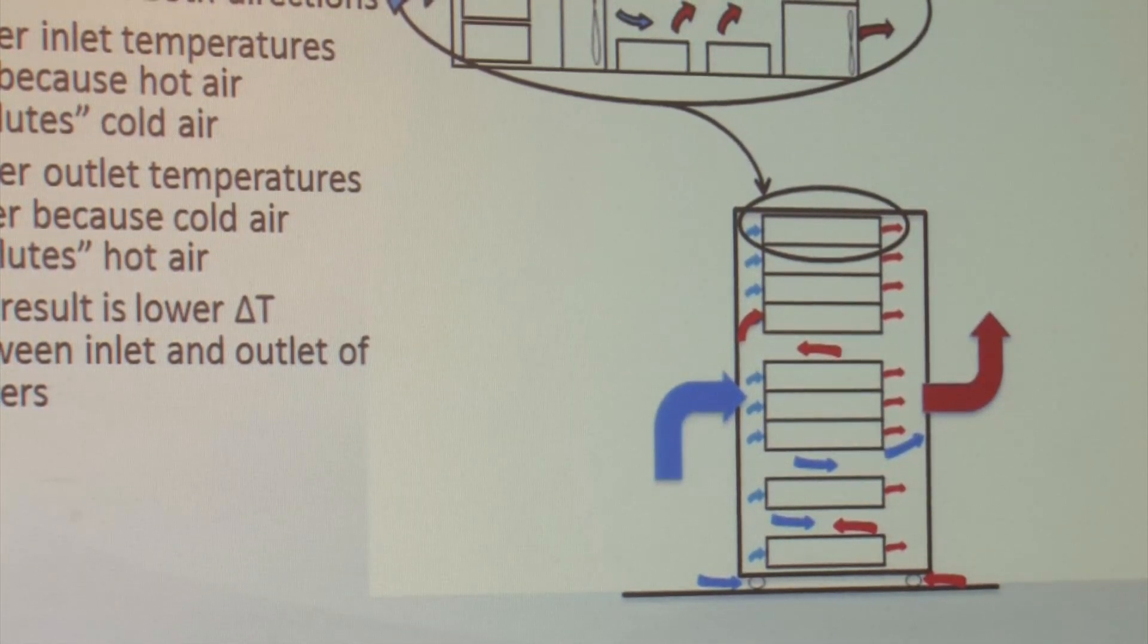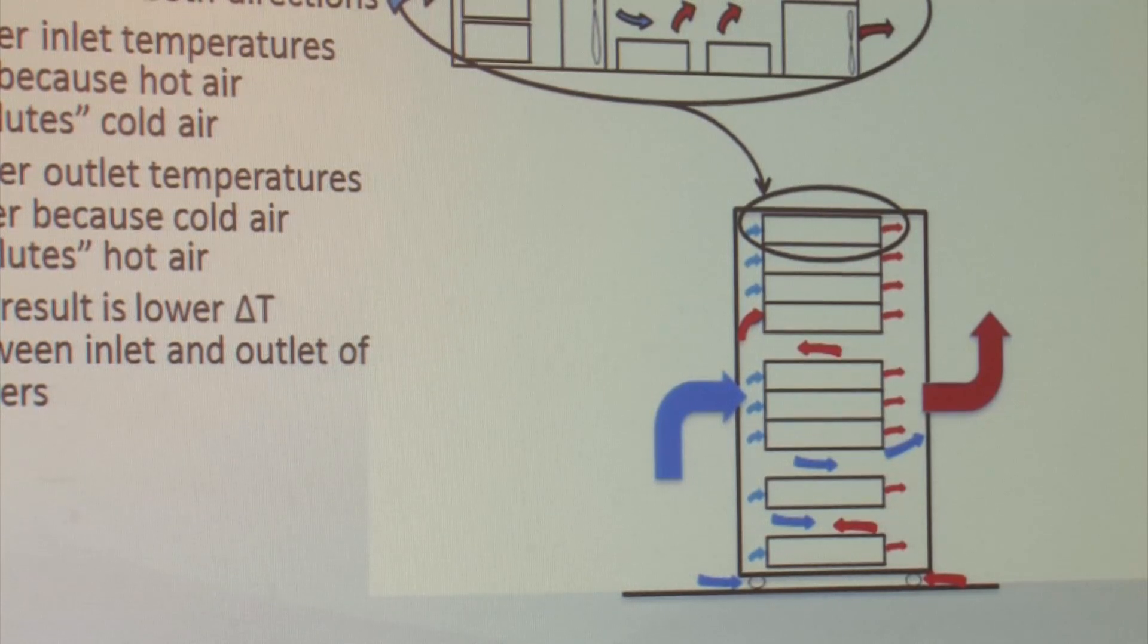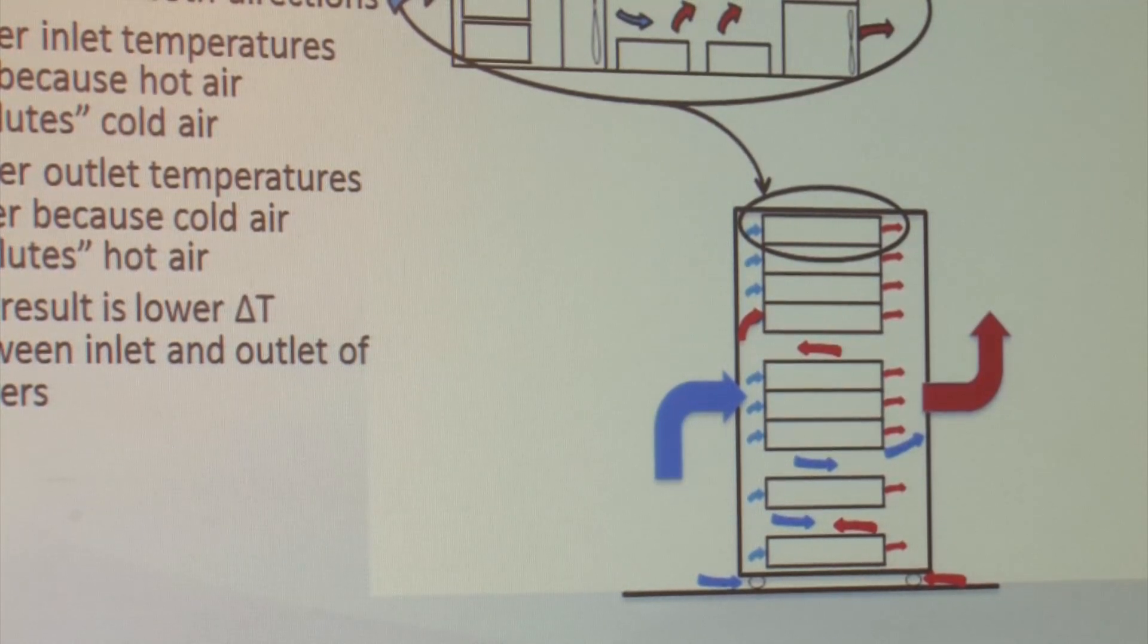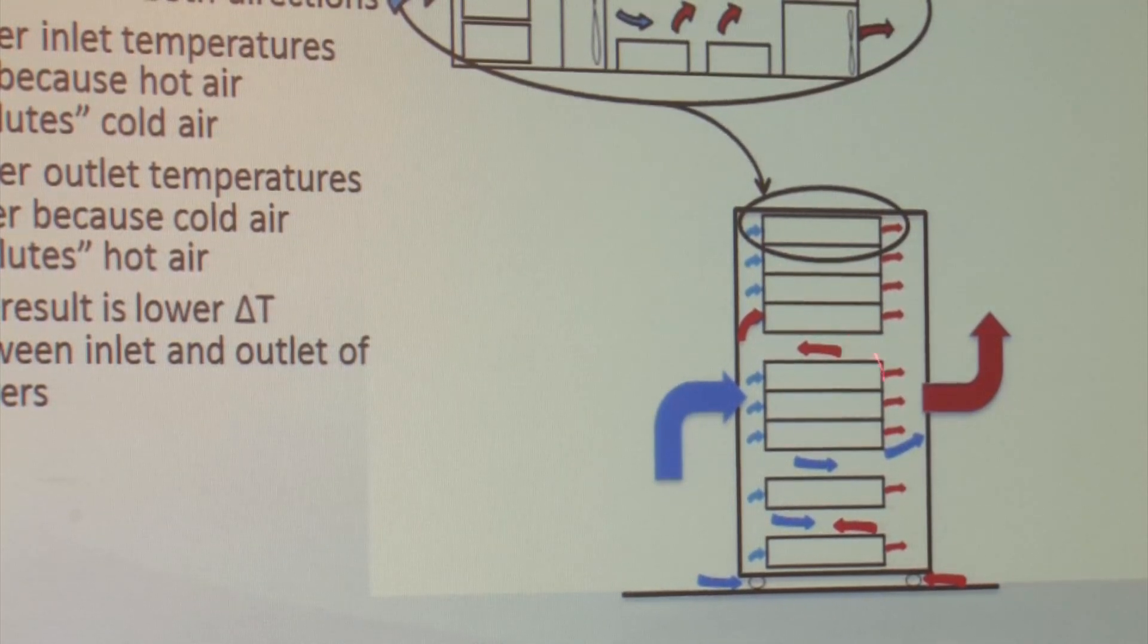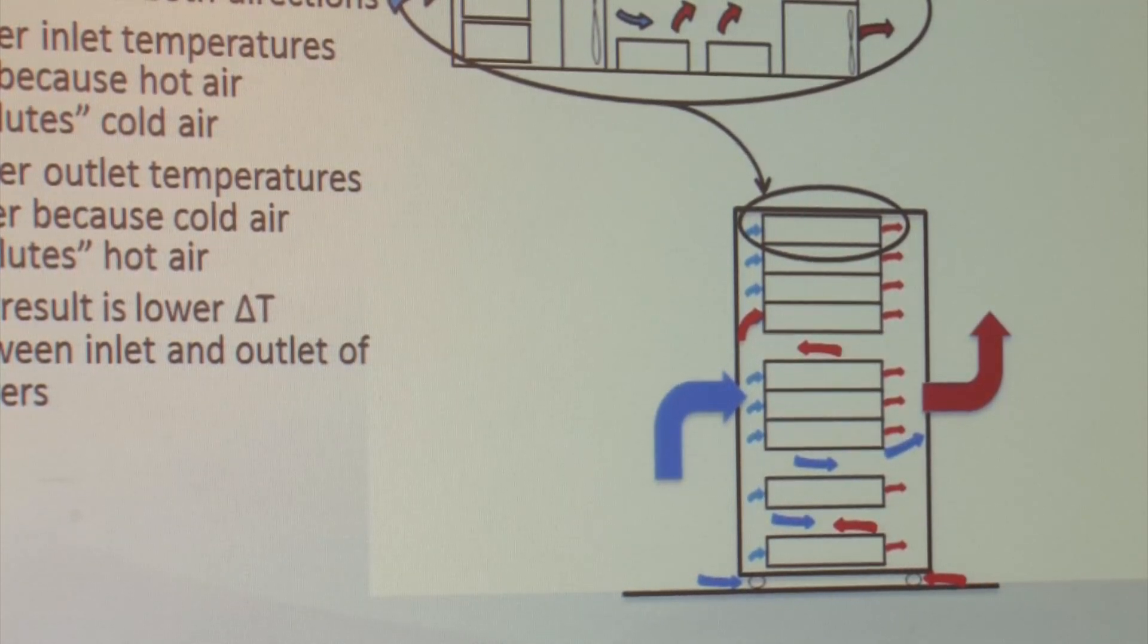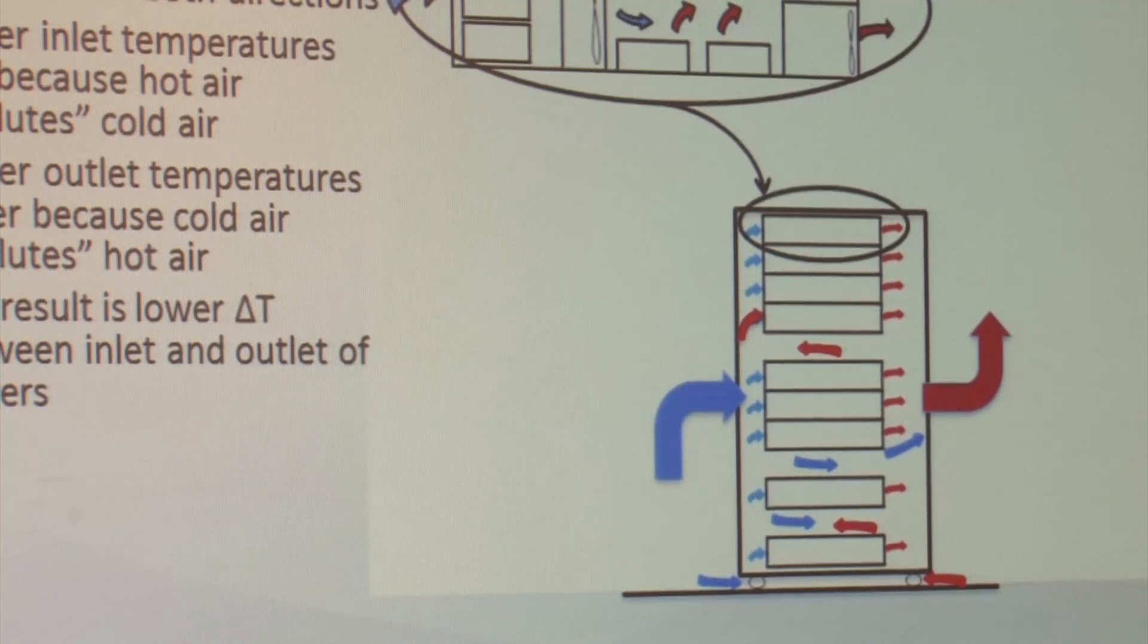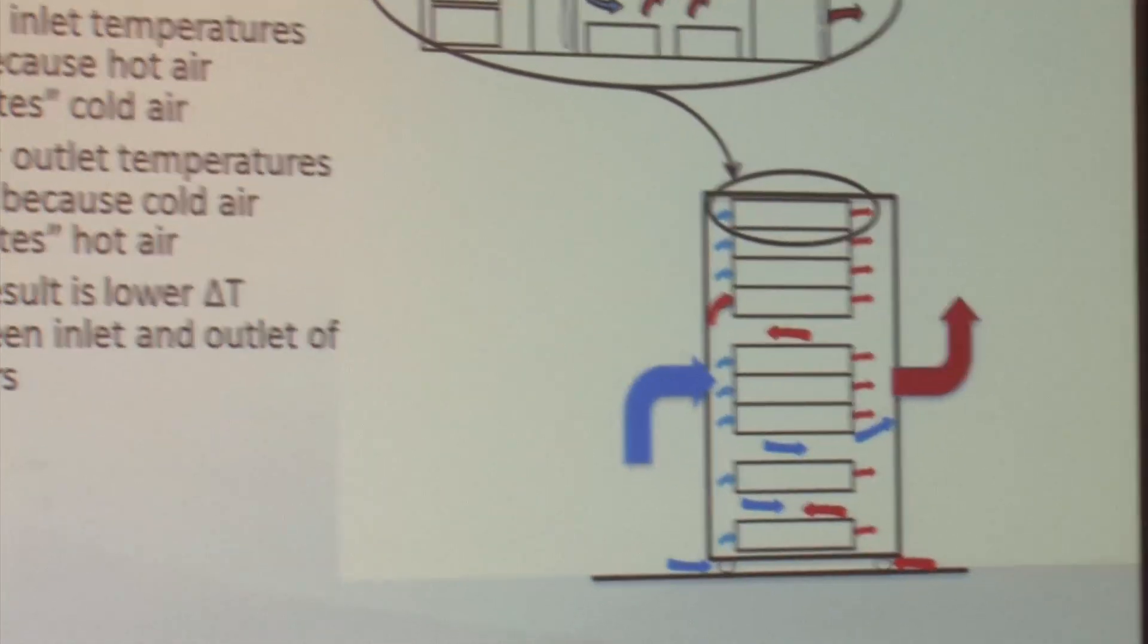In most cabinets, it's imperfect airflow. And I show gaps between the servers as they stack. But quite often, there's also gaps between the rails within the server. A lot of cabinets don't even have side panels. So you mount the servers on some rail or rack and you can see a gap. You can see daylight all the way through. There's a lot of internal recirculation. Whoops. It's very likely that that air comes back along the sides. And it messes up my perfect condition. Darn it, I hate imperfect conditions.